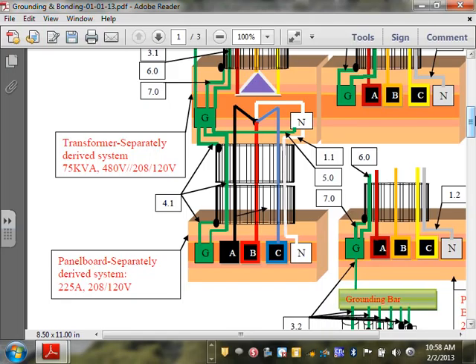Yes, sir. You talked about doing that on both ends, right? Both ends. And the reason for both ends, guys, if you read through the requirement too, is because under a fault condition, both of them are going to be carrying equivalent ground conductor current. So if you do it on one end and you have a high ground fault, this is a 2000 amp switchgear, you have a ground fault at 480, it pushes a lot of energy.